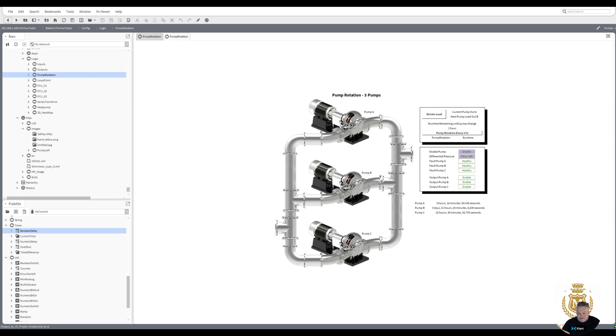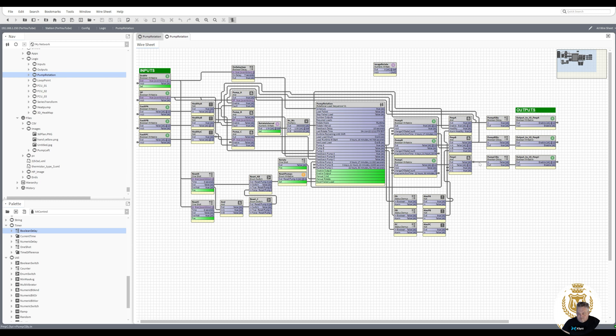I don't know why pump A has decided to rotate. Current pump out: A, next pump out load: B. I really don't know why that has decided to do its rotation — unless we fired it twice. Yeah, must have done, because pump A is going to be the next one running. We must have fired that twice by accident. Pump B is the next one that's going to be running again.